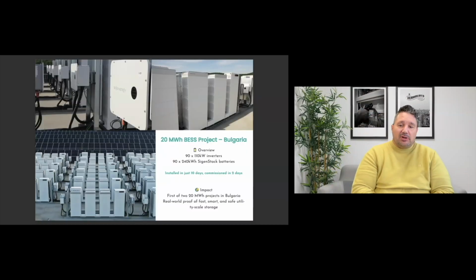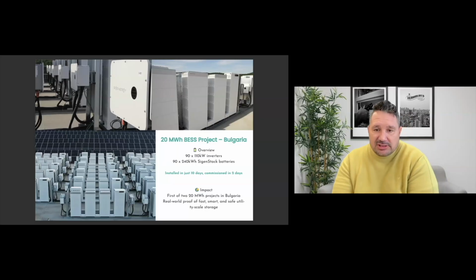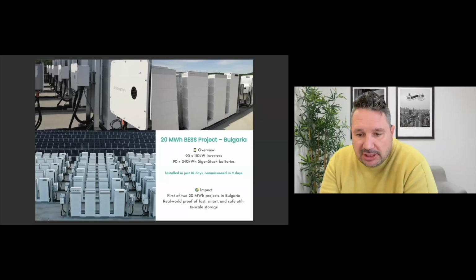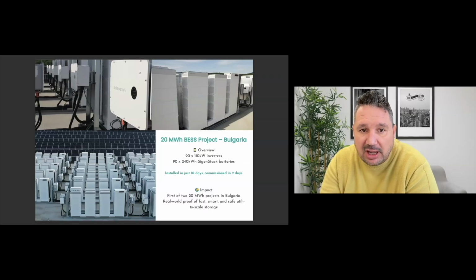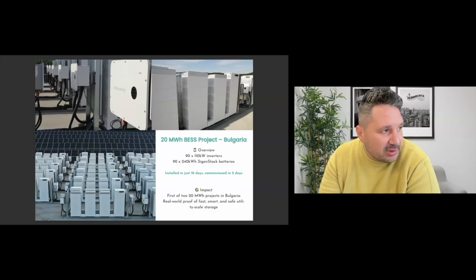This is the project that I spoke about earlier. This project is one of two 20 megawatt hour projects in Bulgaria. It was built with 90 by 110 kilowatt hybrid inverters and 90 by 240 kilowatt-hour SigenStack batteries. As I mentioned, the stack was built within 10 days, as you see it in the picture below, and commissioning took 2 days. If you look at residential or smaller commercial systems, the AI helps you with the commissioning.